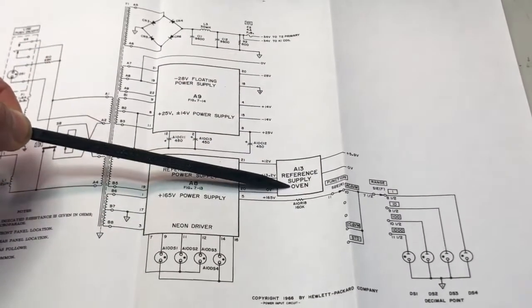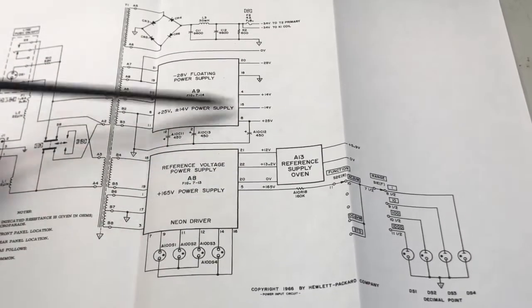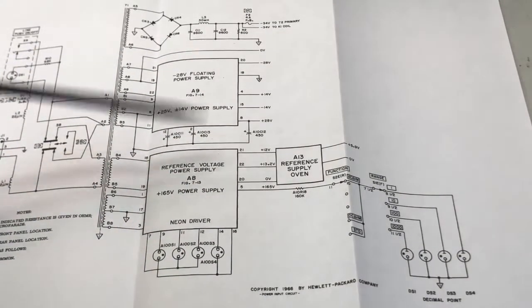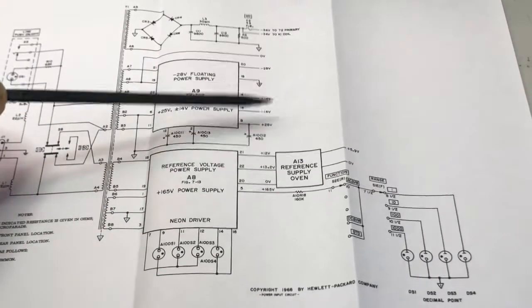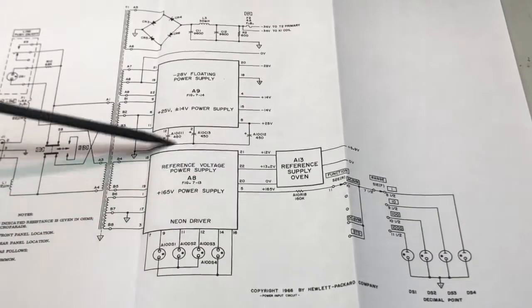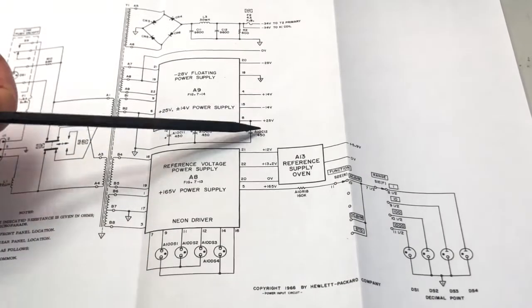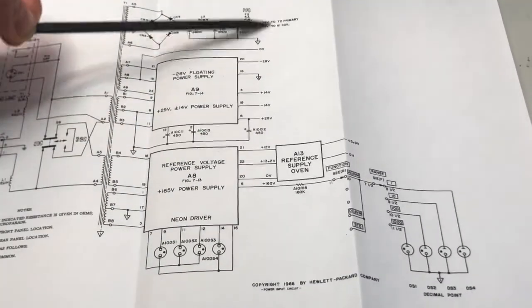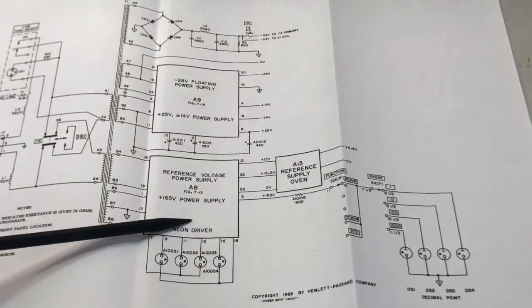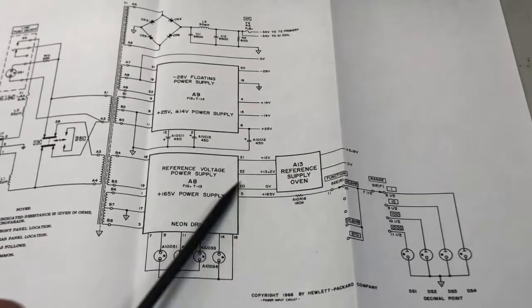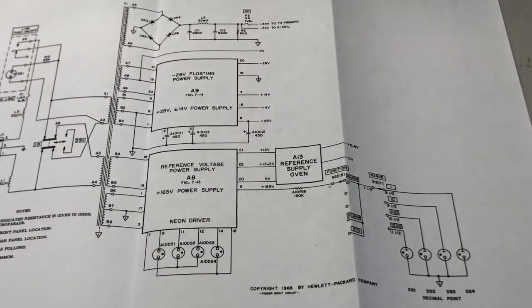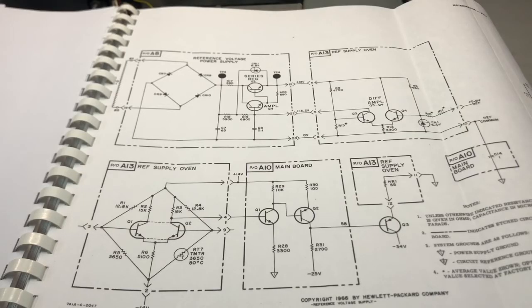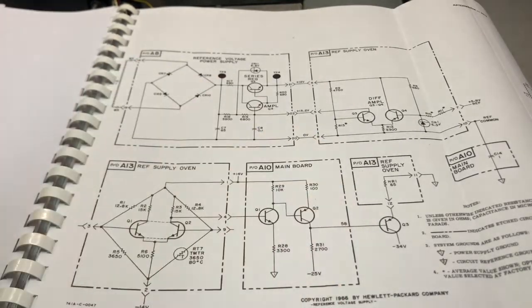So in this case, it's not quite easy to check all the voltages together while I'm powering up and increasing the input voltage. So what I will do is remove this board, isolate it, and check only this side. Later, if everything is fine here, I will plug this board back in. So I will check the other part, and then we will see the behavior of the instrument. And just to be sure that removing the A8 board will isolate this one, I checked the schematic, and indeed, by removing the board, everything on this side will be isolated.